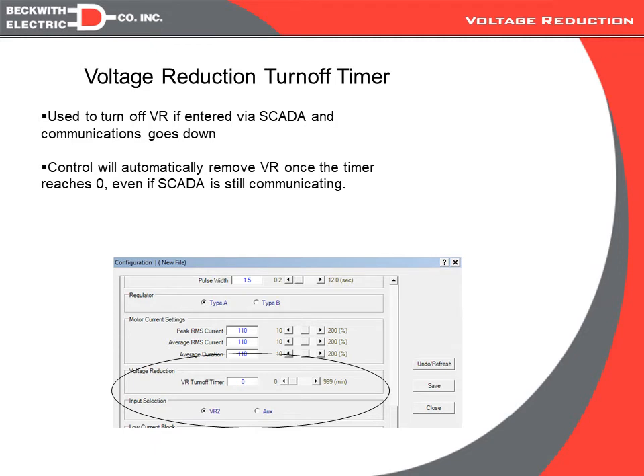Now, if we're going to do reduction from SCADA, we want to make sure that there's a means to turn it off if SCADA communications goes down after issuing it. So if we issue a voltage reduction command for level 2 to SCADA, and we want to come out of reduction, but we cannot communicate to that control, then we're going to have to send somebody out locally to bring it out of reduction. So one thing we've done is we've added a timer, and the way this timer works is if you set it to any value other than 0, then what's going to happen is once SCADA issues a voltage reduction command, the control will stay in reduction for that amount of time and then immediately come out of reduction, even if you're still communicating. So if you're still communicating and you want it to stay in reduction longer, you have to resend that time.